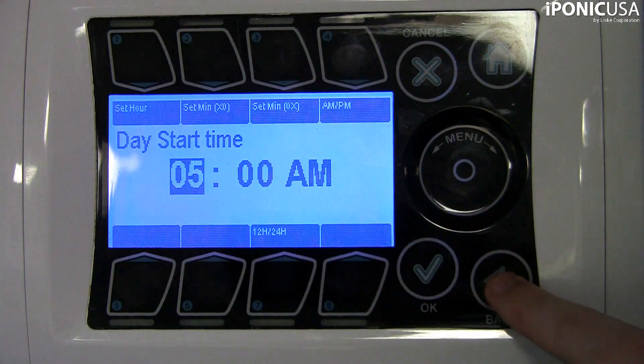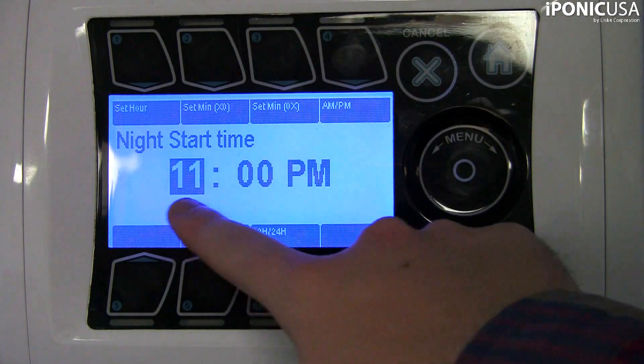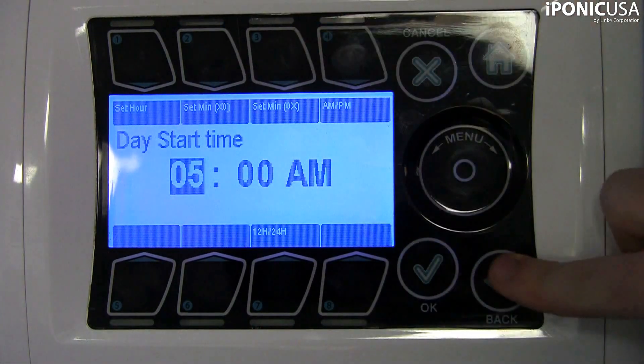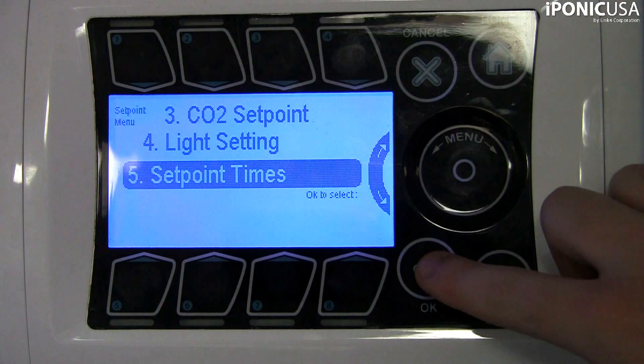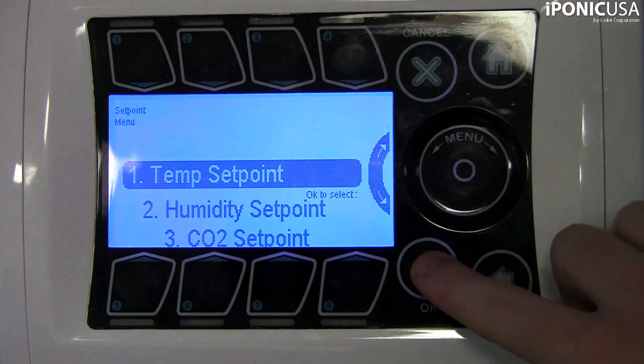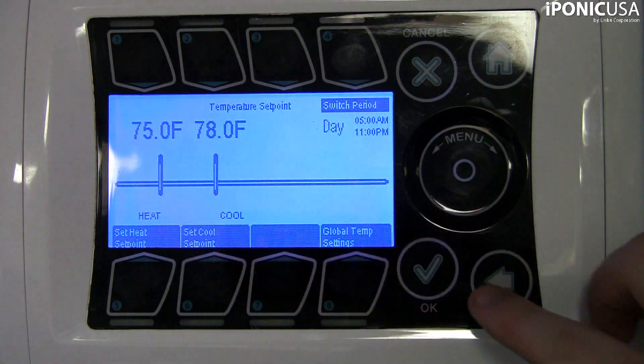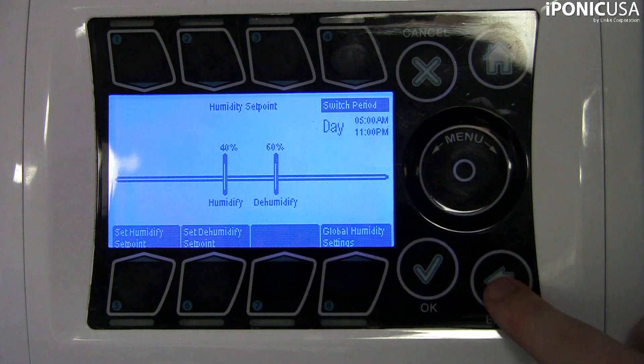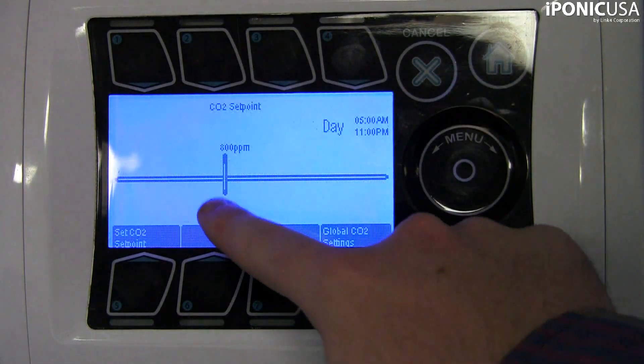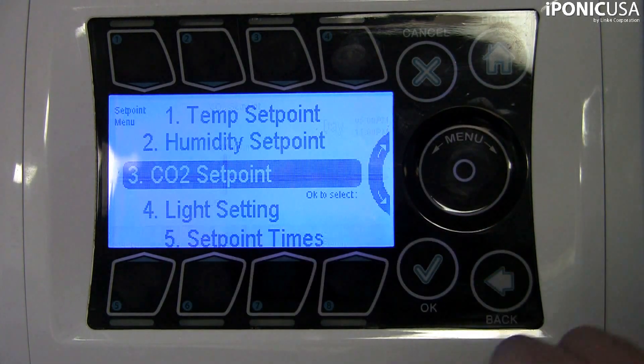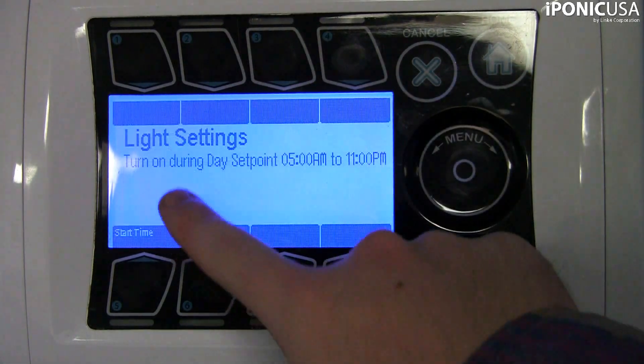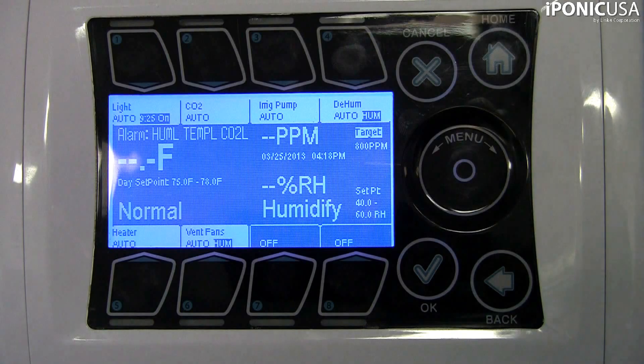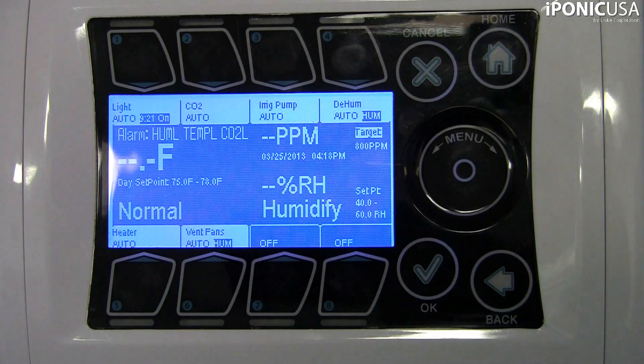You can use up to three time set points in a 24-hour period. To recap, the day set point starts at 5 a.m. with a temperature range from 75 to 78 degrees Fahrenheit, humidity from 40% to 60%, CO2 at 800 ppm, and lights on. The night set point starts at 11 p.m. with a temperature range of 65 to 85 degrees Fahrenheit, humidity from 40% to 60%, CO2 off or at 0 ppm, and lights off.